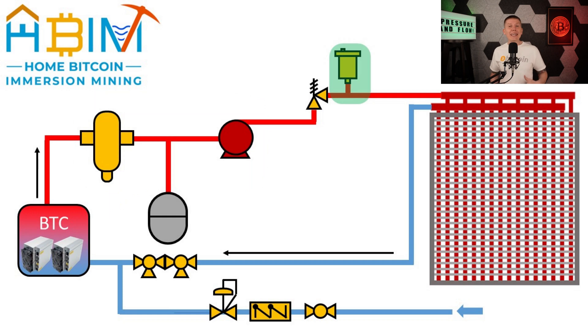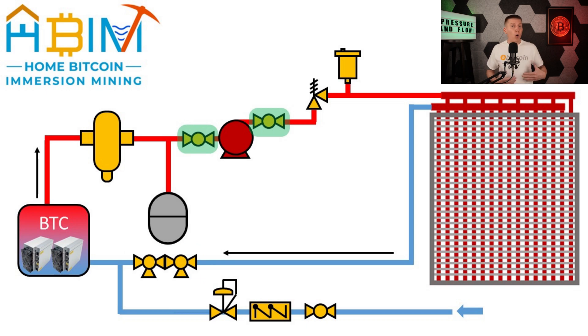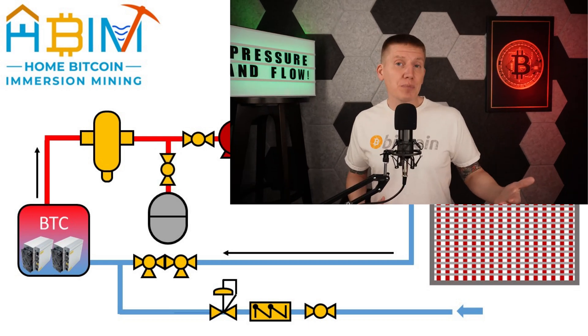An air vent should be located at any high point in the fluid loop to help entrapped air escape. When it comes to other valves, these can be added anywhere where it makes sense. Filling and draining valves are a good idea to make it easy to get fluid in and out of the system. Putting valves before and after the pump is also a good idea so you can easily service or replace the pump. And adding valves before and after major components can also be helpful to isolate them if you have to drain other parts of the system.